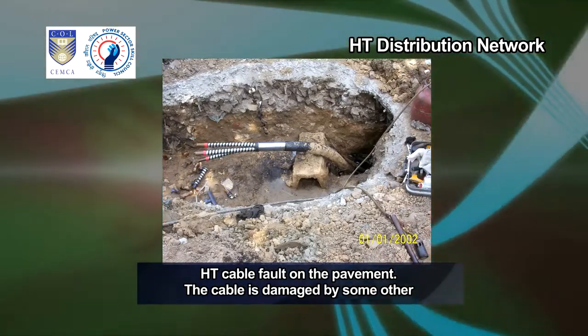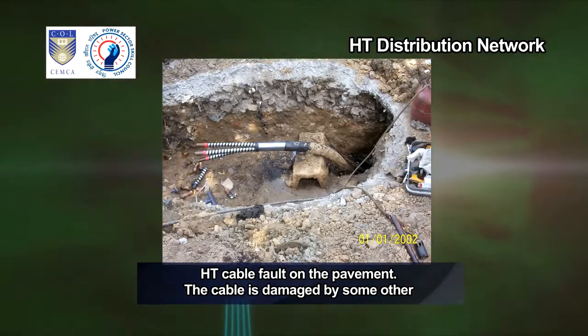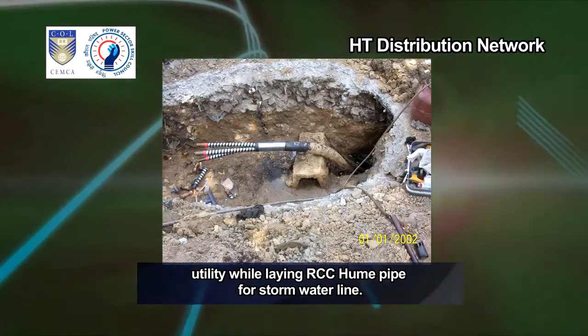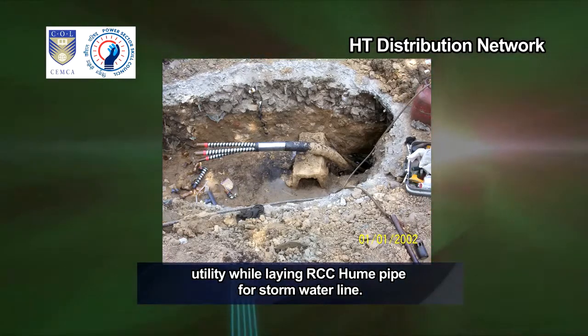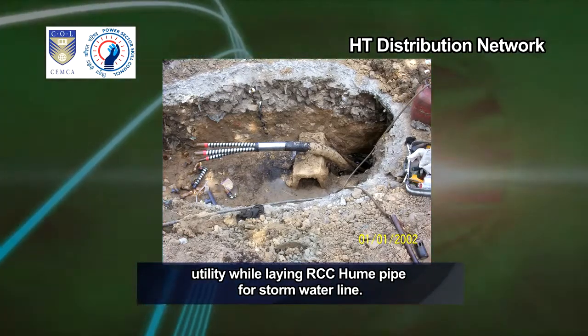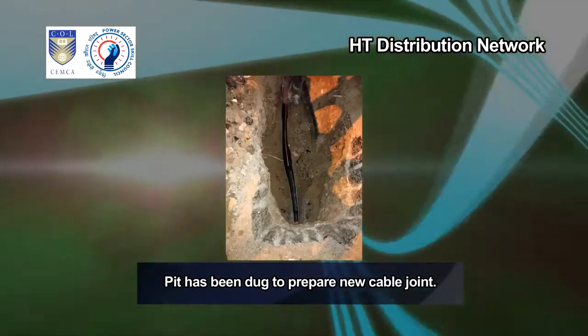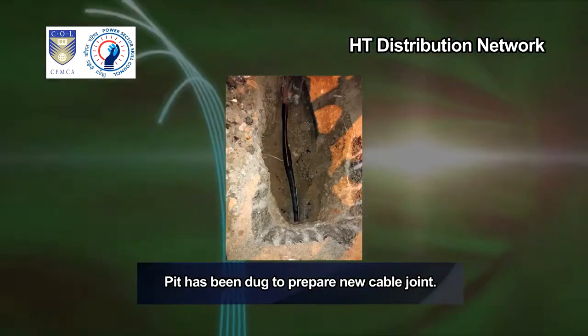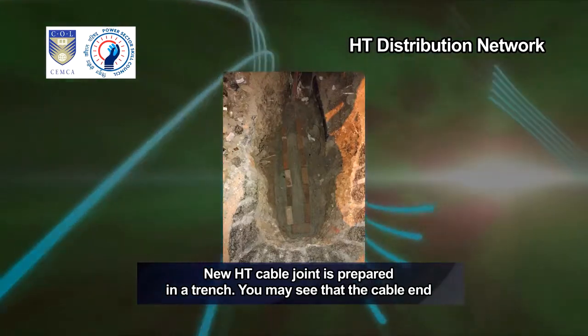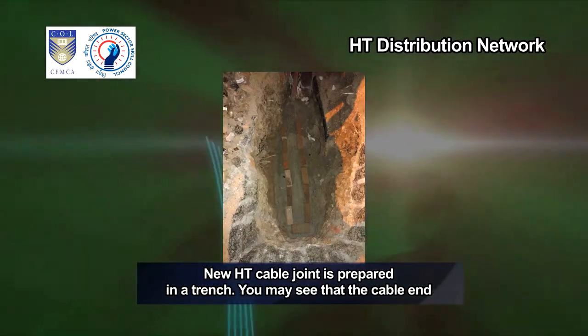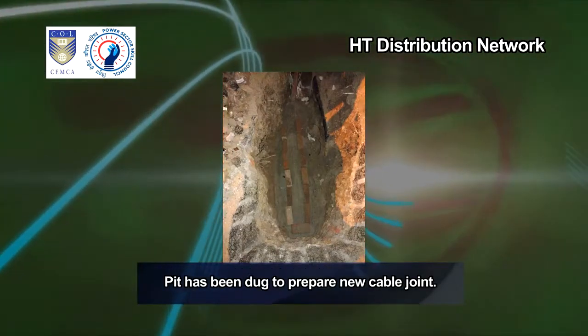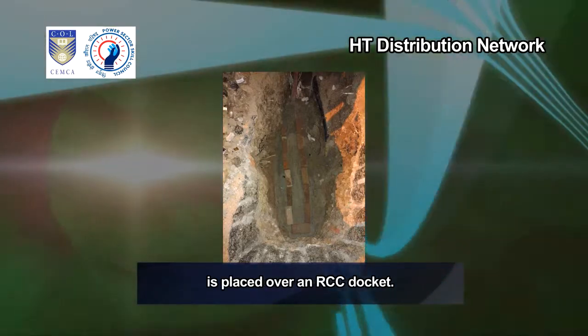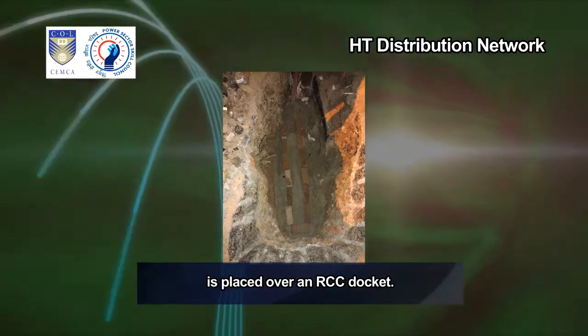HT cable fault on the pavement. The cable is damaged by some other utility while laying RCC Hume pipe for a storm water line. A pit has been dug to prepare a new cable joint. A new HT cable joint is prepared in a trench. You may see that the cable end is placed over an RCC duct.